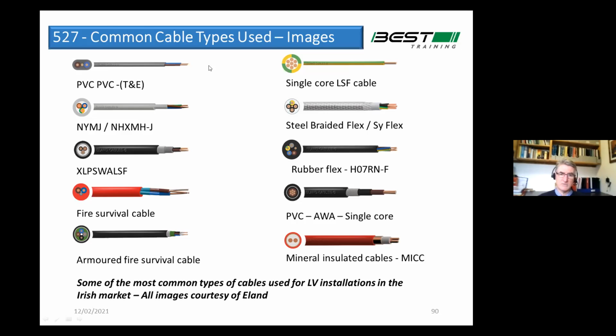So from domestic twin and earth type cables, NYM-J and so on, SWA and fire survival signal cables, then fire survival power cables, and so on and so forth. I put these together in a spreadsheet and sent them off to one of the manufacturers in the UK and said, can you confirm if these cables are available to meet our new minimum requirement, Dca-s2,d2,a2? And not only did he come back and answer me, he came back with the product reference codes the next day. So I was greatly relieved to hear that not only were they available, the manufacturers had told me the product specification code.